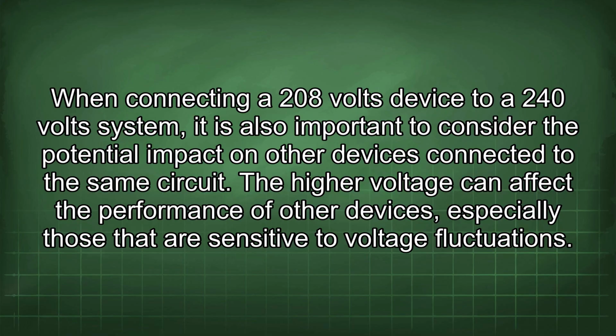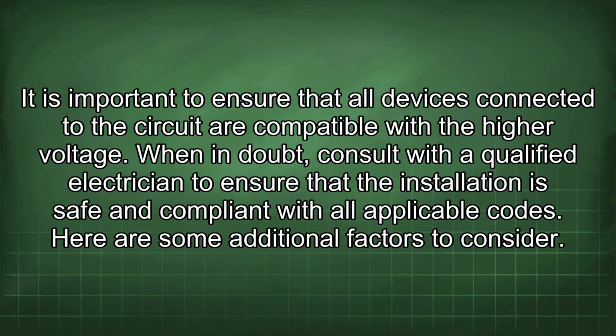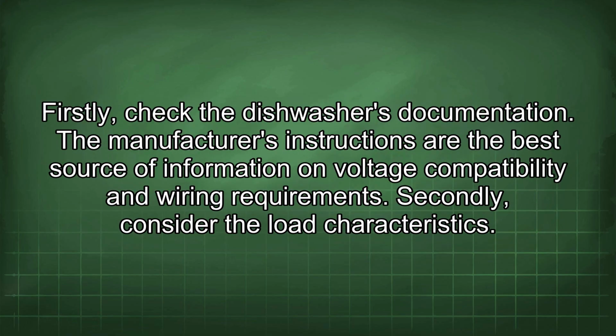The higher voltage can affect the performance of other devices, especially those that are sensitive to voltage fluctuations. It is important to ensure that all devices connected to the circuit are compatible with a higher voltage. When in doubt, consult with a qualified electrician to ensure that the installation is safe and compliant with all applicable codes. Here are some additional factors to consider. Firstly, check the dishwasher's documentation. The manufacturer's instructions are the best source of information on voltage compatibility and wiring requirements.